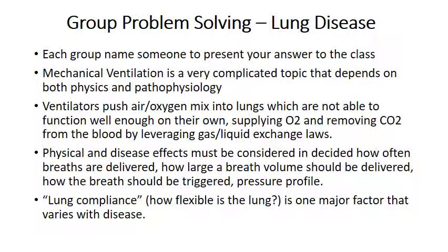Now realize that the way this can work with respiratory therapists or specialists is they're not actually out there doing complicated computations. In many cases, the ventilators have become so intelligent in terms of calculating how to deal with different scenarios that the machine itself is doing all the thinking. And you may encounter, if you get a newer ventilator, something that becomes very difficult to diagnose because it does have so much intelligence.